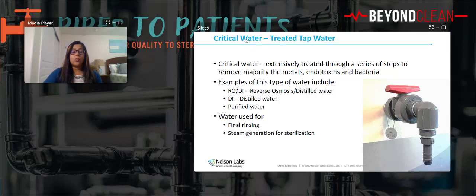Now, when do we use this water? Like I discussed before, we use it for final rinsing and steam generation for sterilization. That's what you want to remember for critical water. My final step needs to use this critical water, which has gone through extensive stages to remove heavy metals, bacteria, and endotoxin, so it's safe for the patient to use. There are different steps in water: utility water, treated by the city, and critical water, treated by your facility. That's the distinction between both.